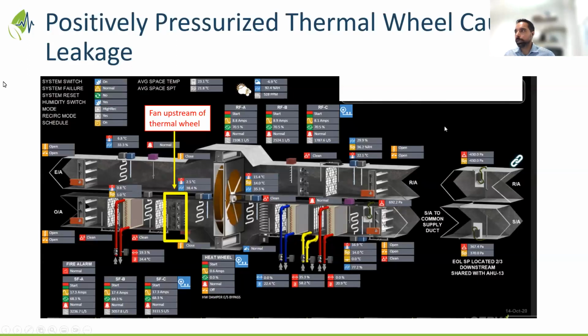This is a positively pressurized thermal wheel causing leakage. This is primarily the issue that we've seen in a lot of AHS facilities, and I think Carrie and I had a conversation about that. It is driven by the design of these units. If you look at most of the Ontario hospitals, the supply fan is downstream of the wheel, so the wheel is negatively pressurized in those cases, whereas pretty much most of the configurations we've seen on the AHS side have the fans upstream of the wheel.